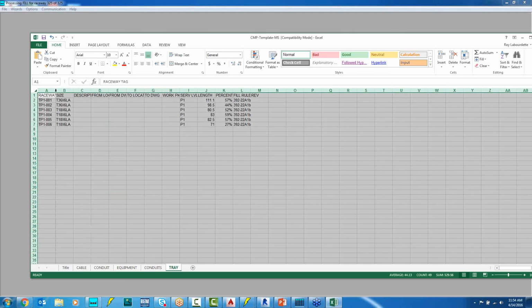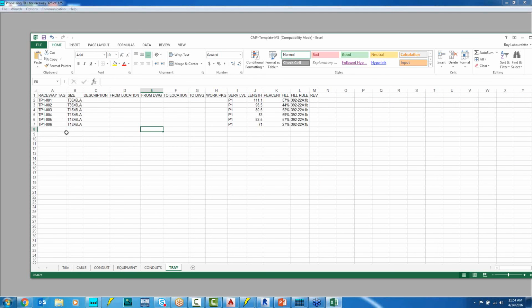And then finally, here's our cable tray. This is a schedule telling us this is a 36-inch wide, 6-inch high ladder aluminum tray, giving us its length, percent fill, and the NEC rule used to calculate that fill percentage.